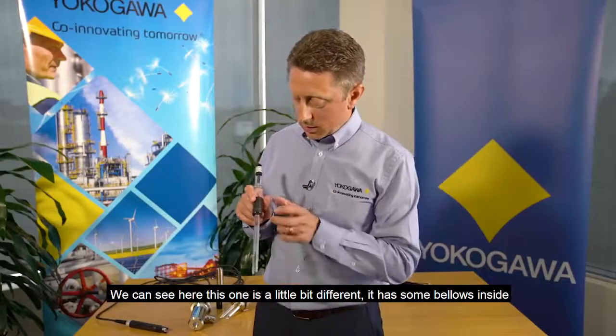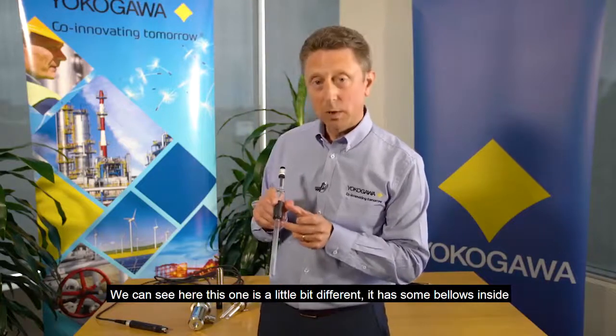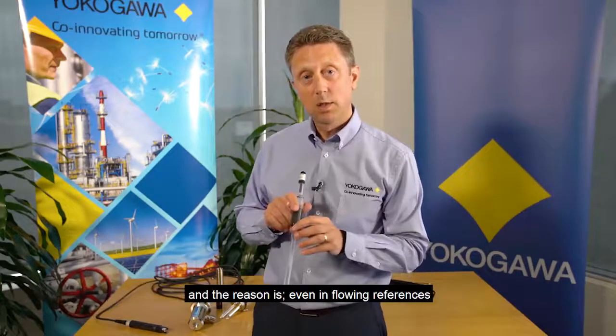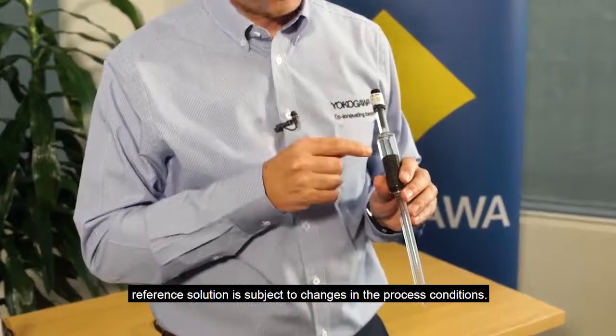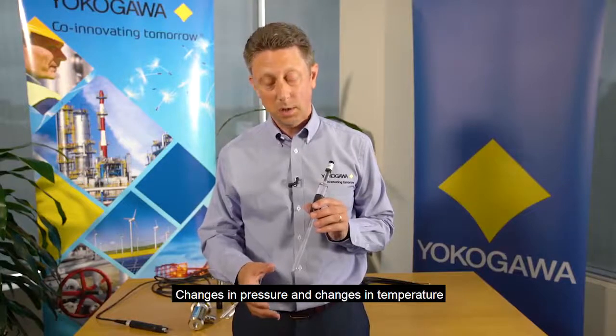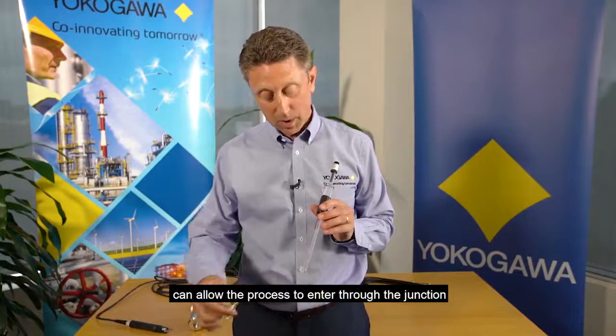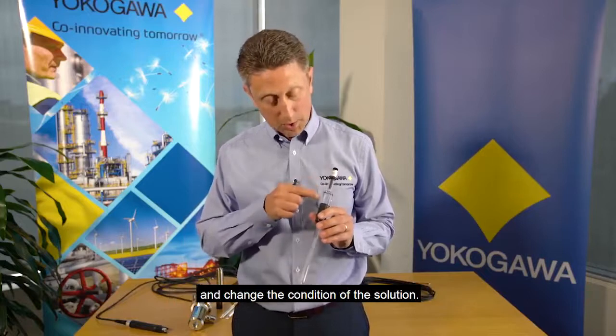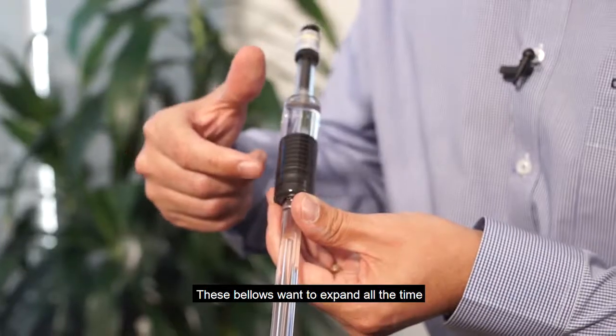We can see here this one's a little bit different - it has some bellows inside. The reason is that even in flowing references, reference solution is subject to changes in the process conditions. Changes in pressure and temperature can allow the process to enter through the junction and change the condition of this solution. These bellows want to expand all the time.